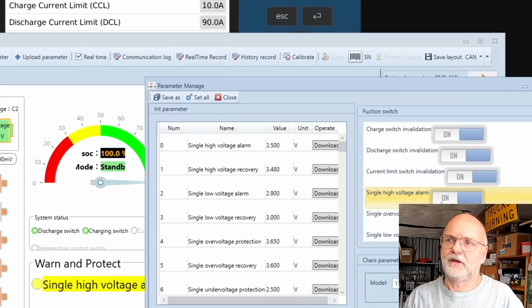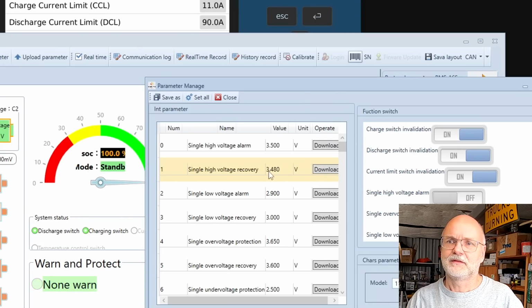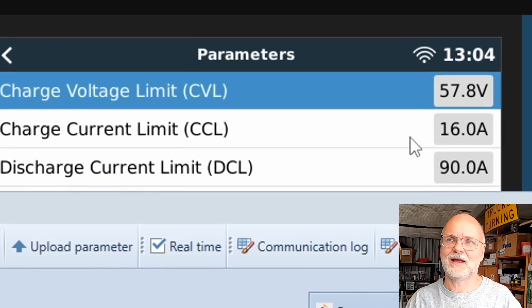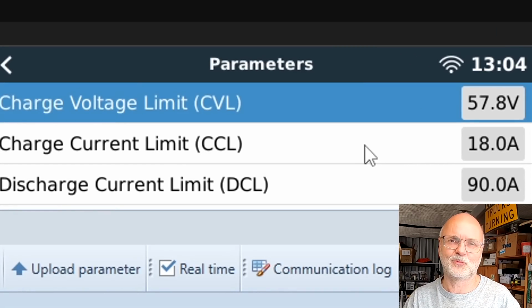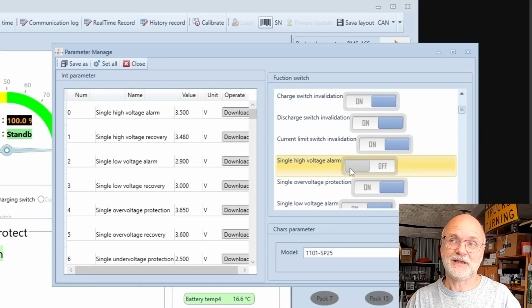Good work. And if I turn off the single high voltage alarm again and write this back to the BMS, the warning disappears and my charge current limit goes back up to 50 amps as it was before. Disabling this high voltage alarm also disables the current limiter when the battery gets full.